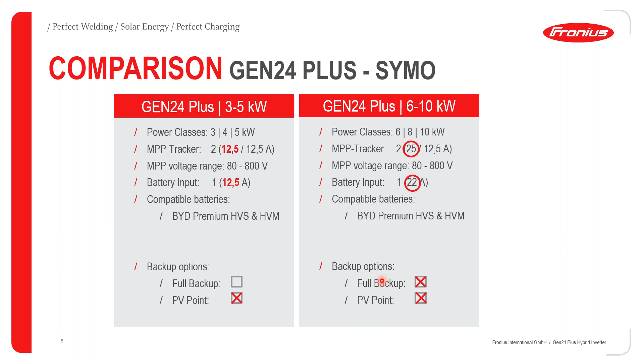The other variation is in terms of the battery connection. So we can see that for the smaller power class Symo Gen24, we can connect up to 12.5 amps, but for the bigger Gen24 Plus inverters, 6 to 10 kilowatt, we can connect up to 22 amps. So the effect that has on the backup options of the two variations is that for the smaller power class up to 5 kilowatts, you do not get full backup out of this inverter, but the PV point is still operational. But for the bigger inverter, 6 to 10 kilowatt Symo Gen24, you get both the full backup application or possibility and the PV point out of that inverter.